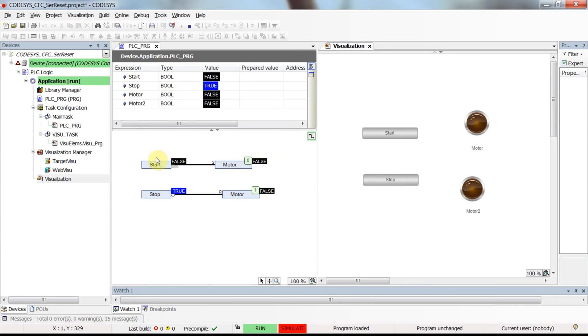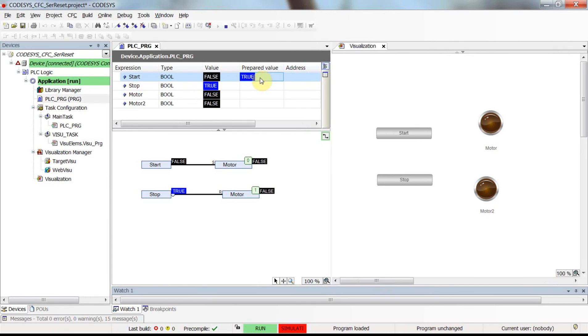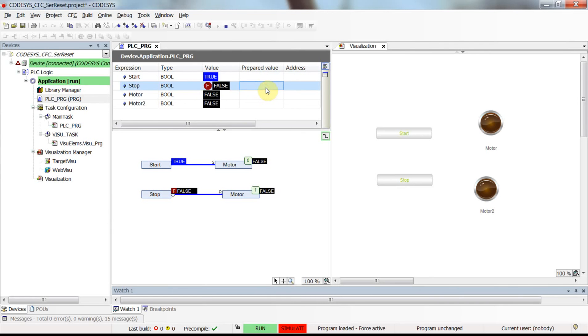If I force the value of start to true and force stop to false, we have the motor being set by start and reset by stop simultaneously. Since the Reset instruction is executed after the Set instruction — it has order 1 — the Reset has priority and determines the final state of the motor.